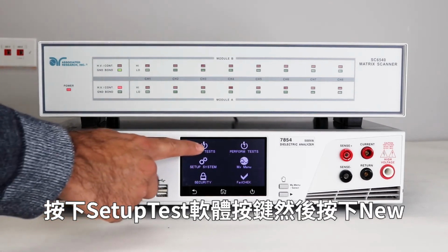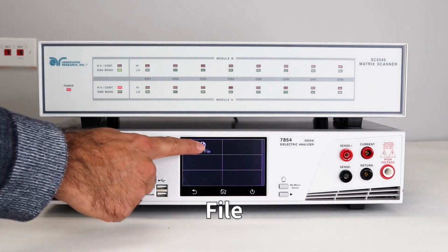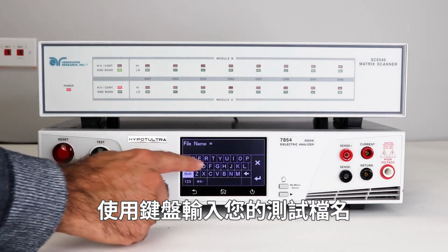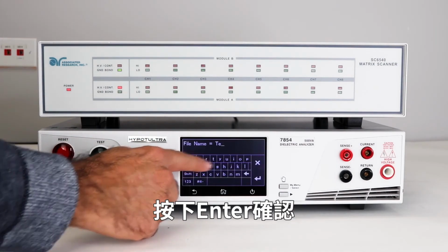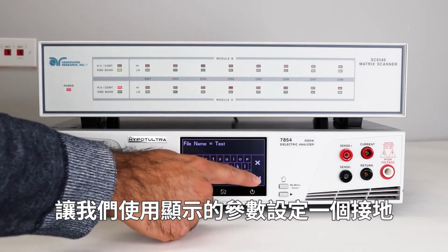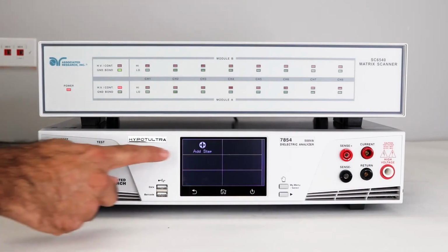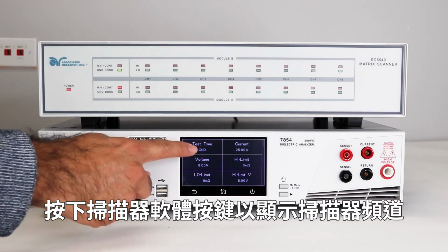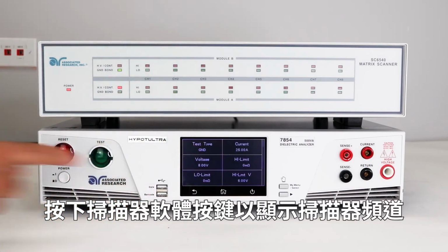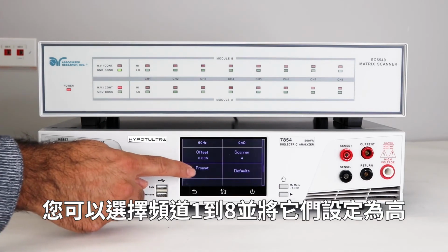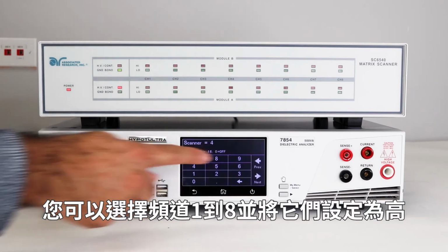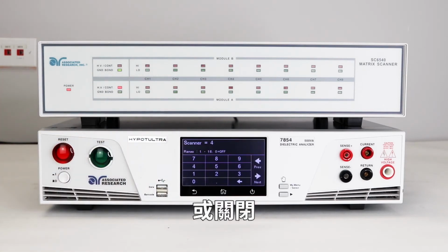Push the Setup Test soft key and press New File. Using the keypad, enter the name of your test file. Press Enter to confirm. Let's set up a ground bond scanner test with the shown parameters. Press the Scanner soft key to bring up the scanner channel screen. You can select channels 1 through 8 and either set them high or off.